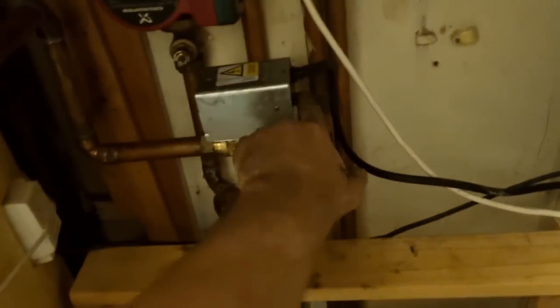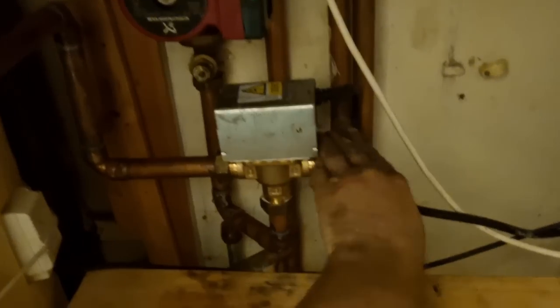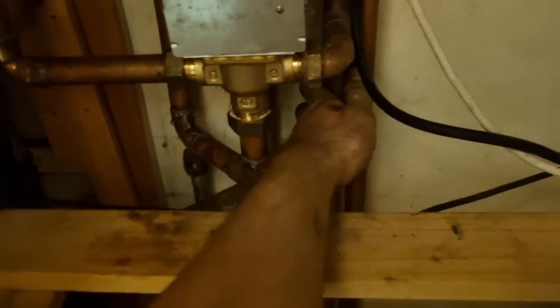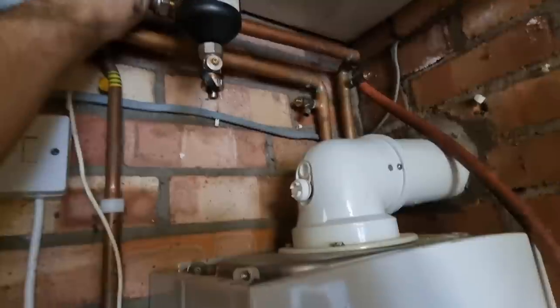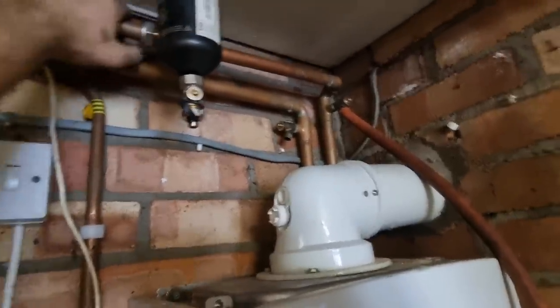We're now getting good temperature everywhere. Pump's got a bit of air in it. That'll purge. Three port working, perfect. I've all completed them upstairs radiators. I'm sure it's good to go. Right, I've had to put a hose on there just to drag it through the return a bit. We're now getting solid return temperature.